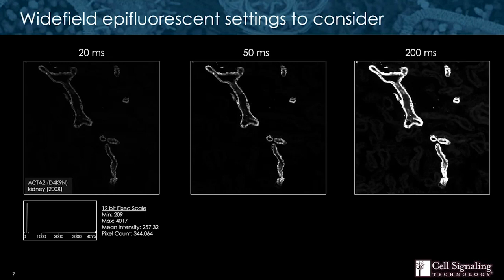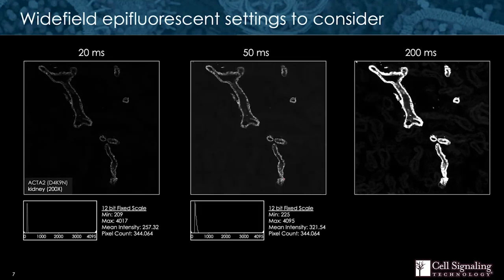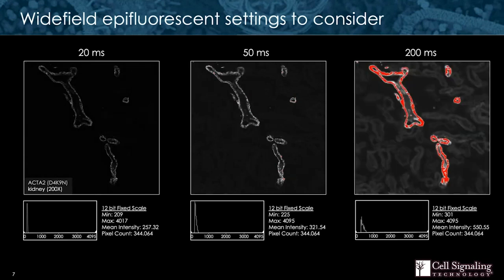When you're trying to decide what exposure time to use, there are a couple of tools you can work with. First, if your microscope software displays histograms, this will be a helpful tool to determine when you're detecting meaningful signal — you want to see a curve with some separation between the start and the end of the intensity. Another helpful tool is the range indicator. Range indicators will typically highlight over- and underexposed pixels in an image. Red is typically shown for pixels that are saturated, meaning the potential well in the camera is full and you won't be able to measure the real value of that pixel. I recommend adjusting your exposure time until you're able to see only a few saturated pixels, because this will allow you to measure the full range of signal in your sample.